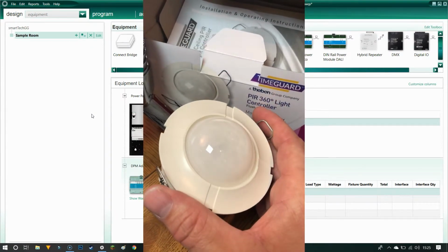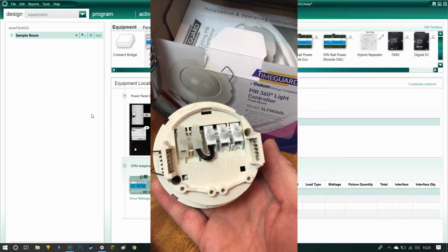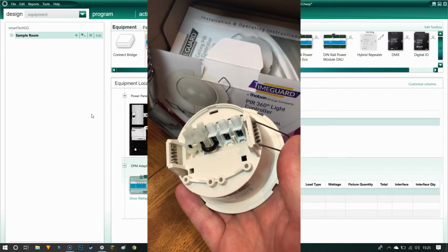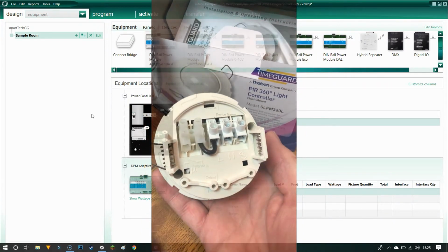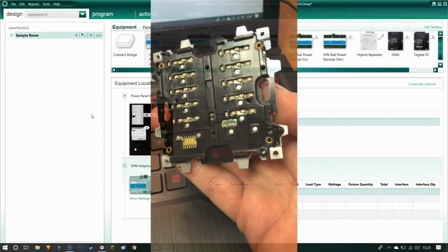a bit like this one. So this is a standard sensor. It's actually by TimeGuard, this one, if you're in the UK. And if you look on the top here, it's got some volt-free contacts. At the moment, there's a little black link between the live and the contact closure on the PIR. But that can be removed, and then basically you will be left with a volt-free contact. And then on the back of the keypad, you will see there is a connection.